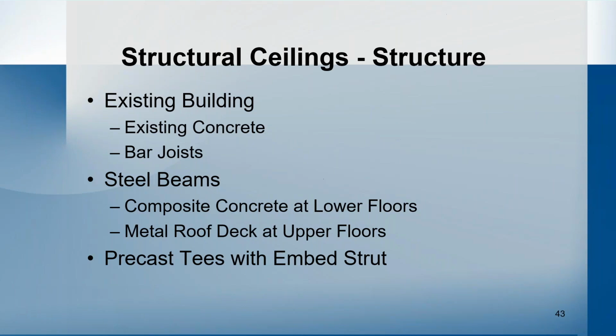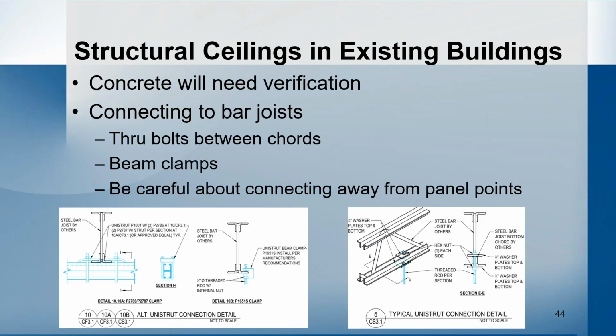So now, what are they exactly connected to? There's a number of different situations. Existing buildings are becoming less frequent, because we've almost exhausted a lot of them and are building new more frequently. But when you have an existing building, you have existing concrete you need to contend with, or bar joists. Other building types have steel beams with composite concrete at lower floors. Sometimes you have concrete at the roof, but often it's metal roof deck at the upper floors. And then precast tees with embedded strut is another common connection.